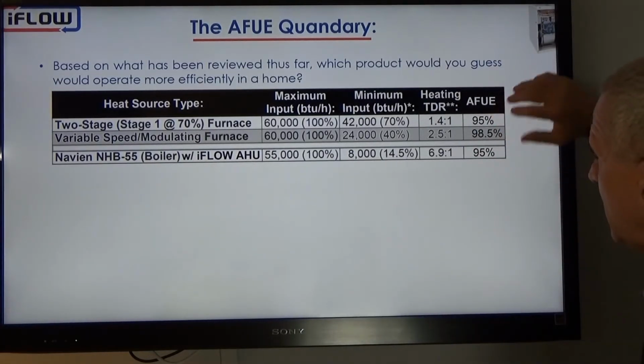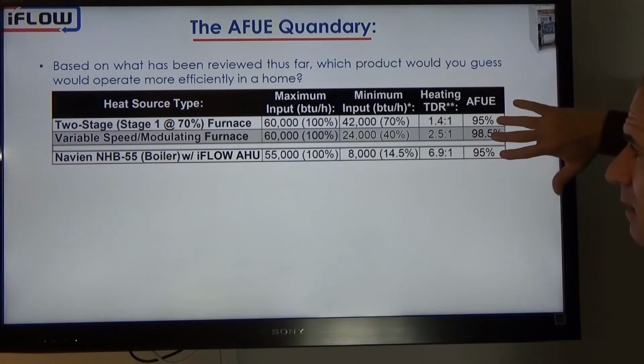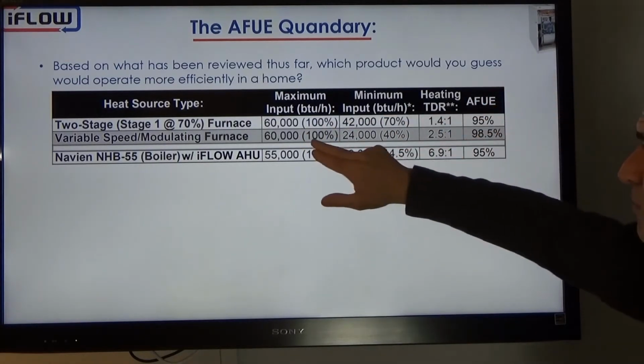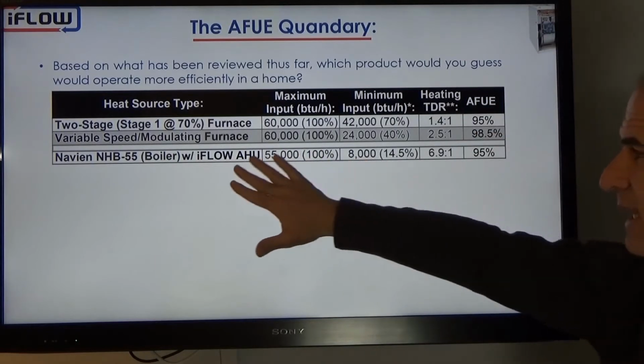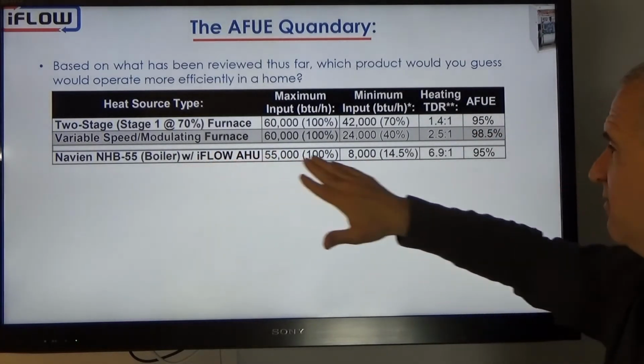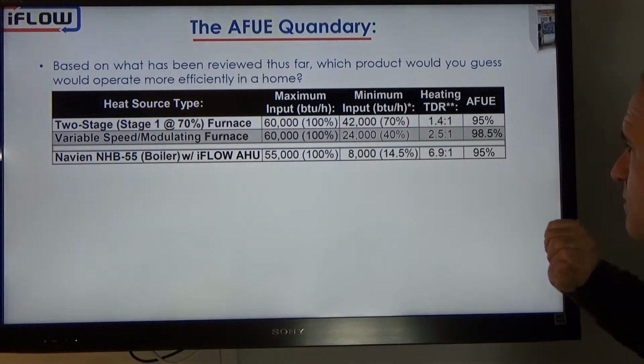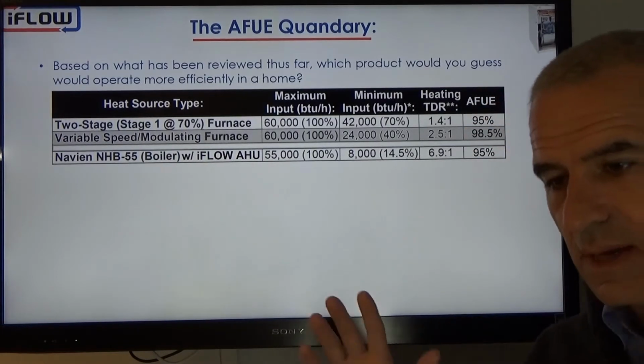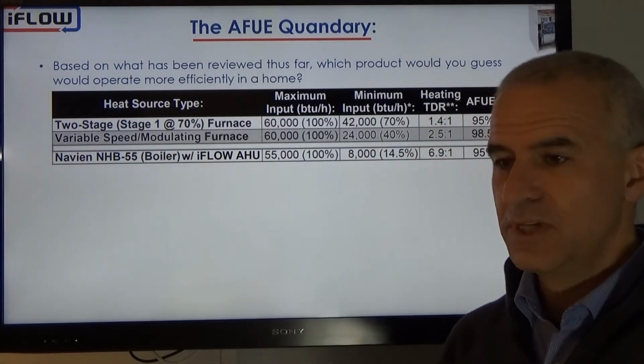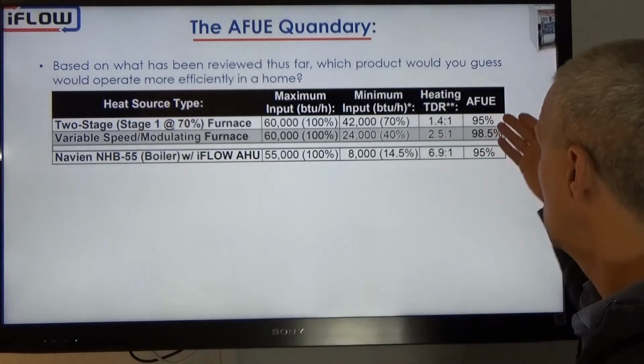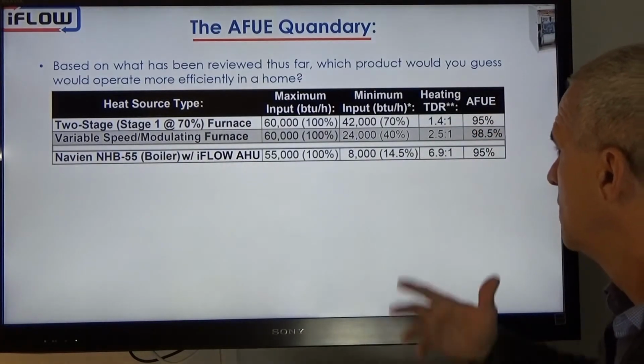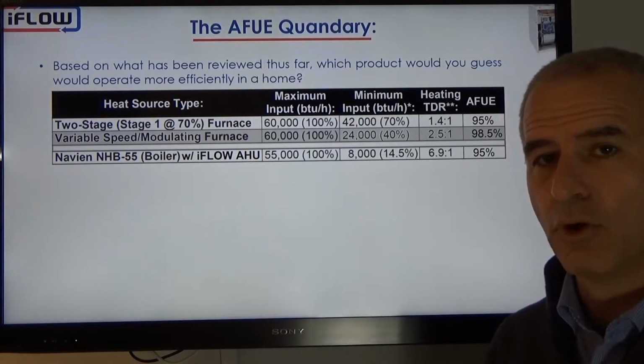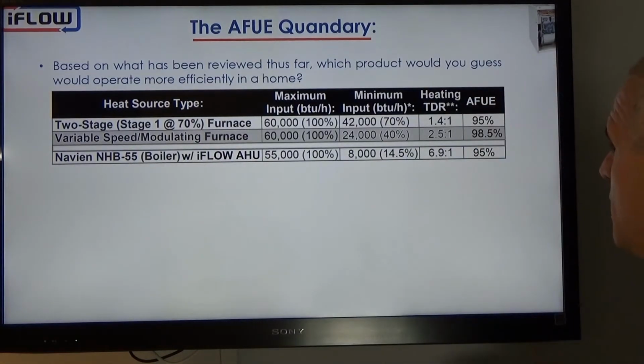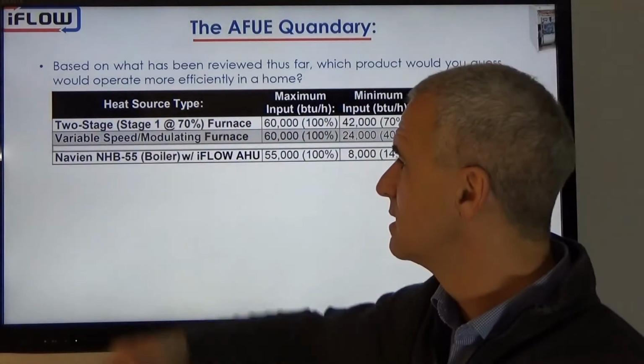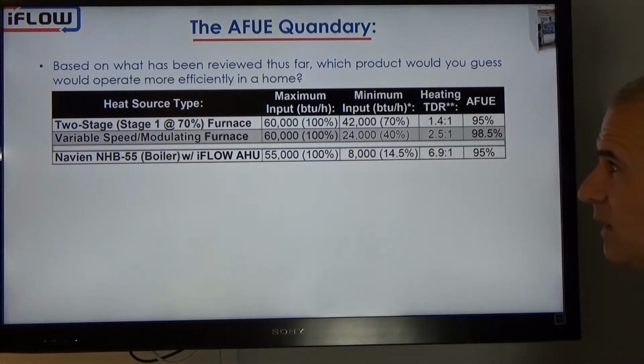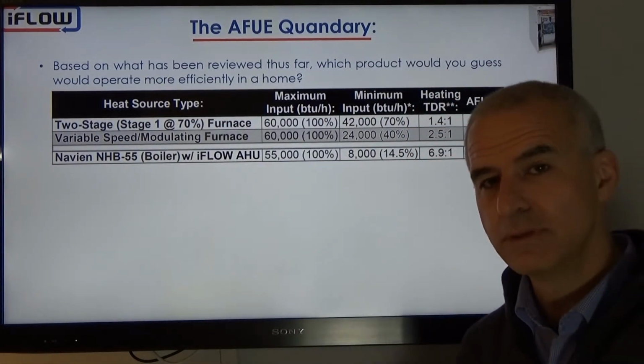So if we're looking only at AFUE, we've got the two-stage furnace at 95, we've got the modulating furnace at 98.5, we have the Navien boiler with the iFLOW at 95%. So conceptually or intuitively perhaps you would say, well, they're all 95 and above. They're all going to be very good performing. They should be great. They should be equivalent. What do you think? Do you think they'll be equivalent?